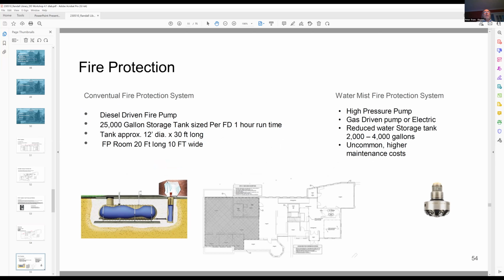So we have two options to deal with the fire protection system. One is a more conventional system where we would have a 25,000 to 30,000 gallon storage tank on site or in an adjacent site. We would then have a diesel-driven fire pump, which would generate water pressure to distribute water into the sprinkler system and ultimately through the sprinkler heads themselves. The tank is about 12 feet in diameter, 30 feet long, and in addition to that tank, you need a fire pump room near or on top of the tank to house the fire protection equipment.